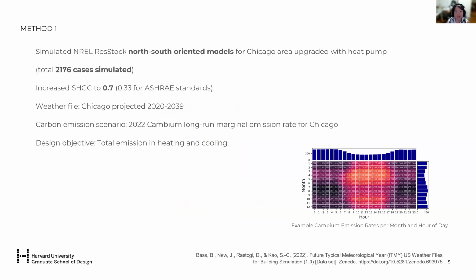During the study time, the ASHRAE recommendation for maximum solar heat gain coefficient for a climate like Chicago is 0.33. So we're basically doubling the amount of solar heat gain. The weather files we use are also projected future files, because we're simulating a future scenario with all buildings electrified. We use long-run Cambium and long-run marginal emission data for the emission case, again foreseeing that future trend. So the objective is to reduce the overall emissions in heating and cooling.